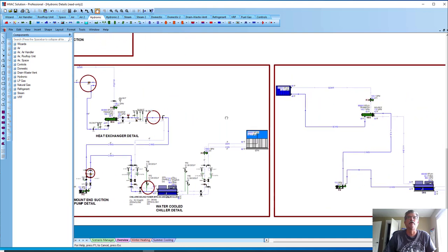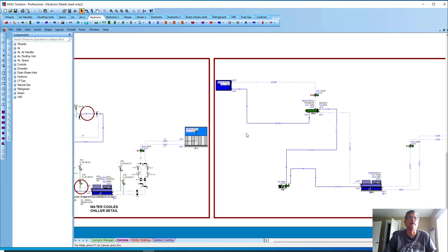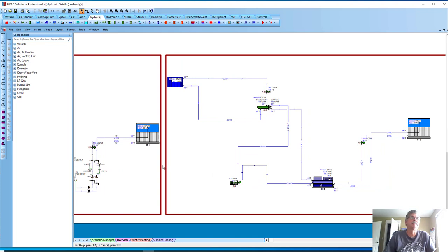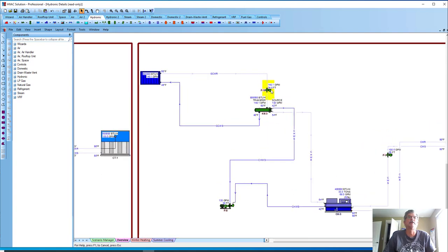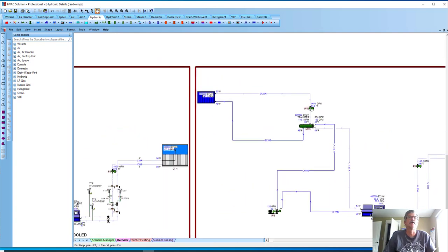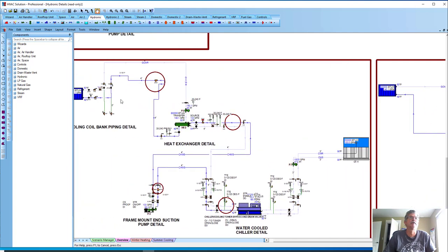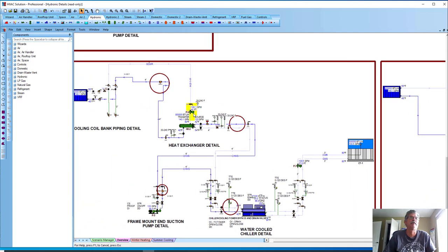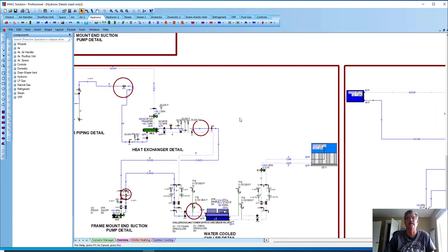Now, the other workflow that's very acceptable, and I do, and it's seen done, is just show all the components without the little miscellaneous valves and all the control features and components. Well, in that case, you look at the head on that pump is 34.8 feet. Let's go look at the other one that has all the components in that was serving that were 45 feet. So in other words, when that goes through it and does a little traverse of the system, it's picking up miscellaneous valves, control valves, strainers, balancing valves.